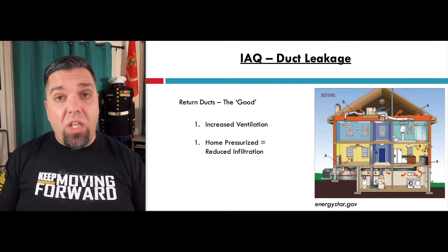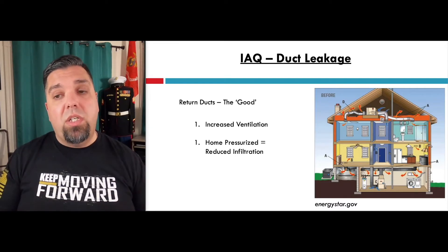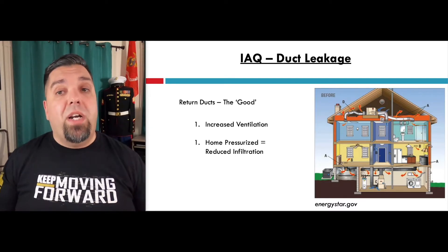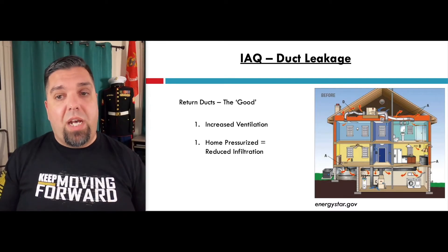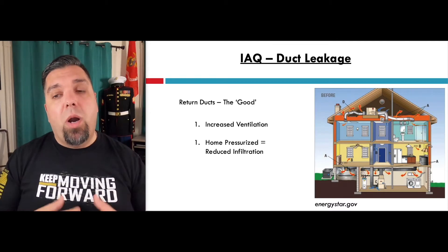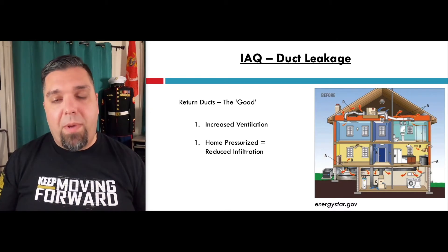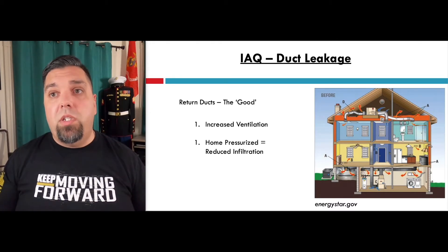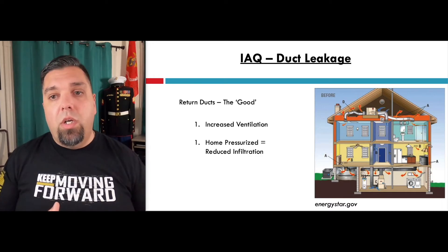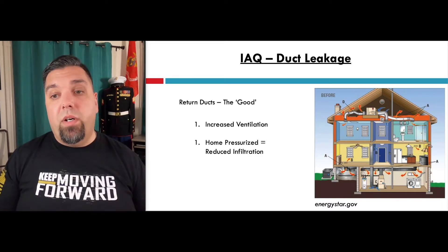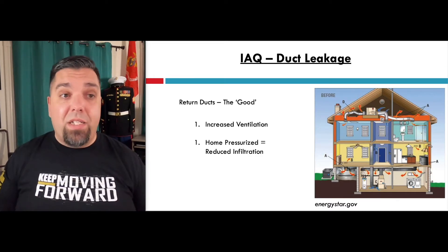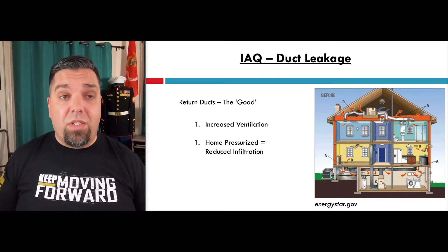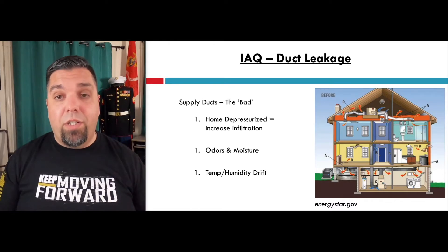So it's really important that when you seal duct work, you do a combustion appliance zone test and make sure you're not pulling carbon monoxide back into the house — whether it's from a fireplace, a hot water heater, or even unvented appliances. There are some of those still out there.